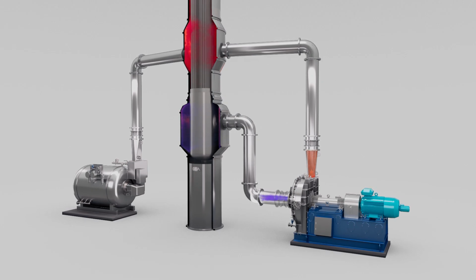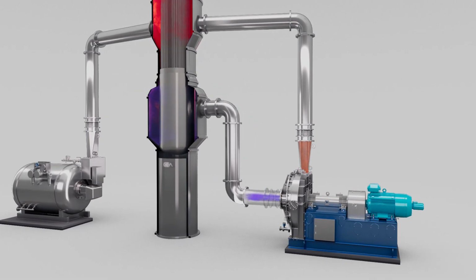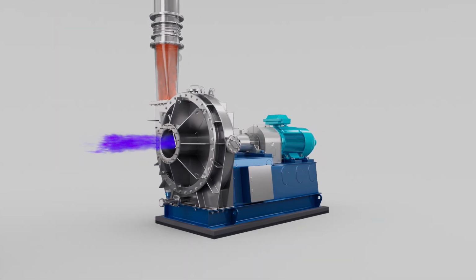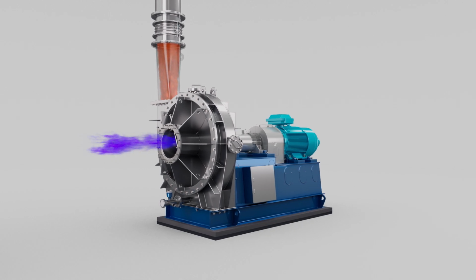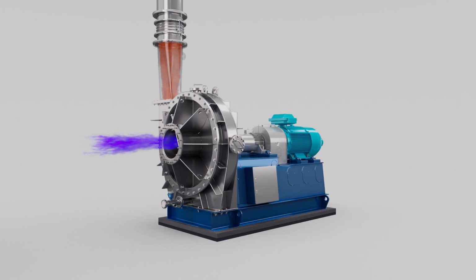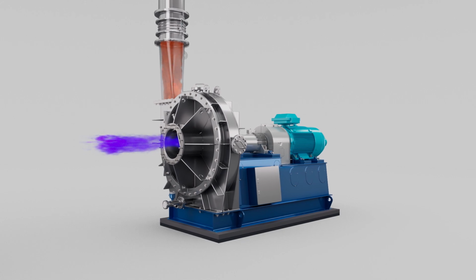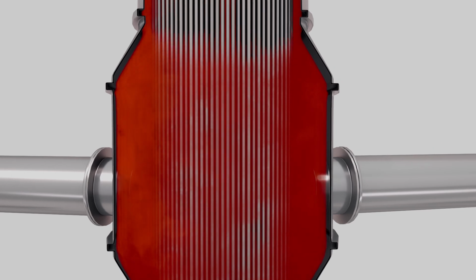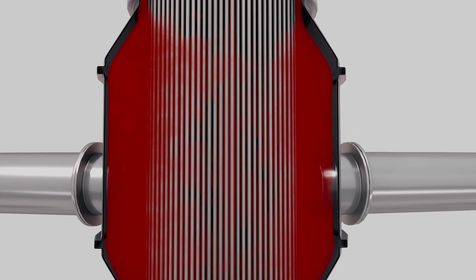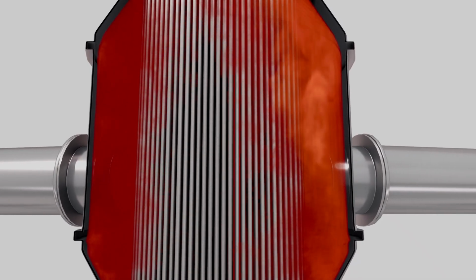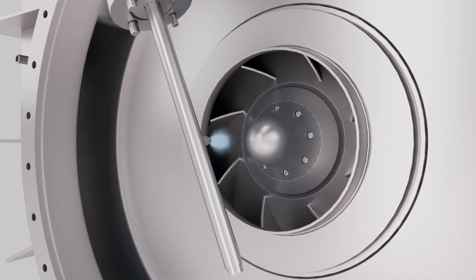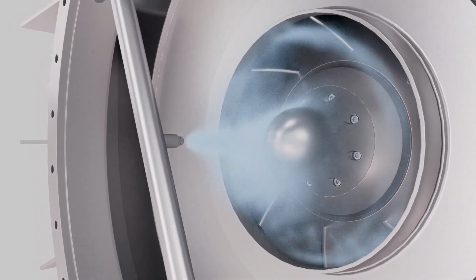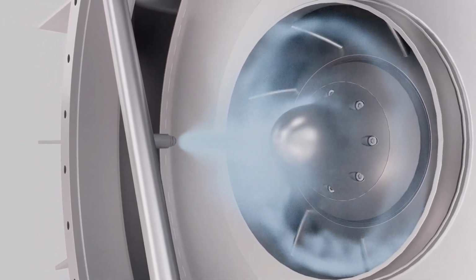The vapor that develops is recompressed in the fan. As a result, its temperature is increased to such an extent that it can be reused in the evaporator as heating steam. The electrical energy fed in is used only to increase the temperature of the existing vapor, not to generate it. This closes the loop, and the steam boiler can be switched off once the system has started up. Cooling the vapor by injecting water at the fan inlet prevents it from overheating during the compression process and ensures it leaves the fan in the saturated state.